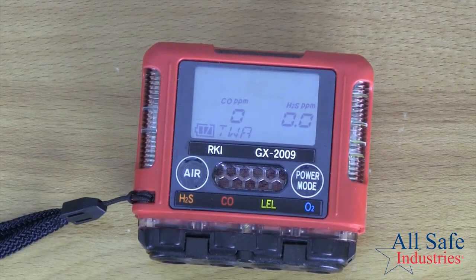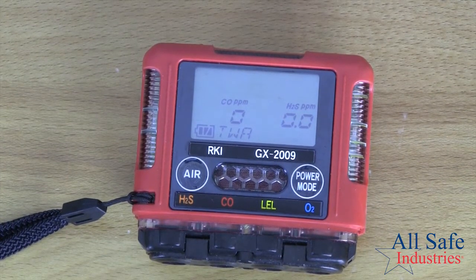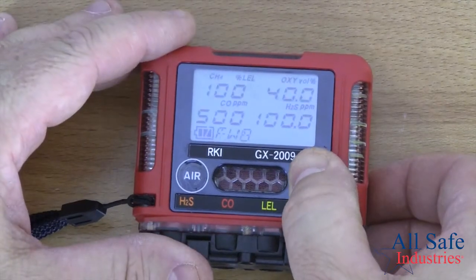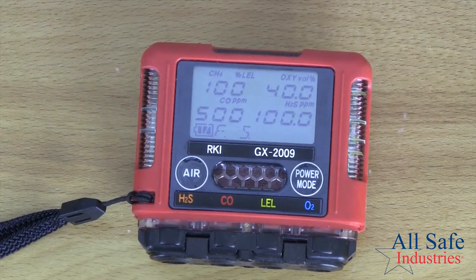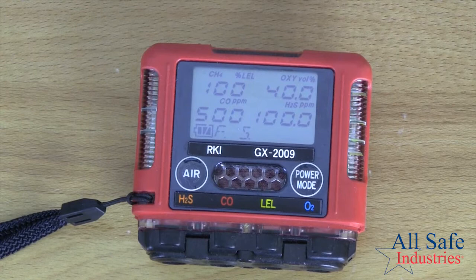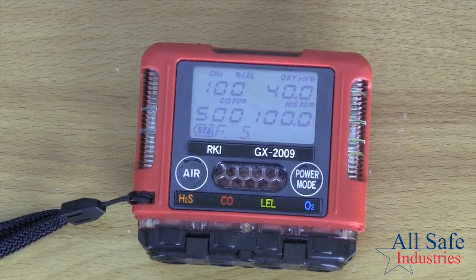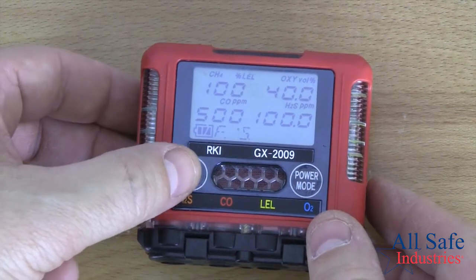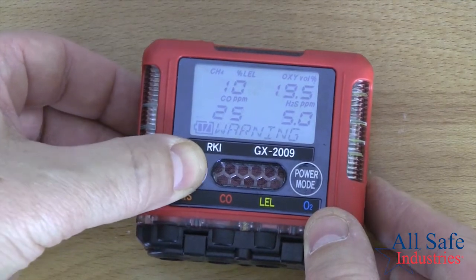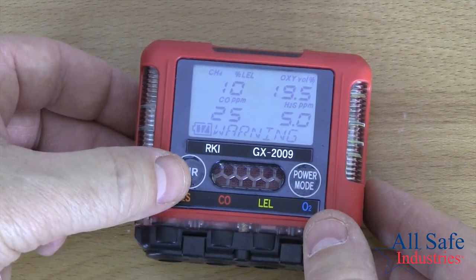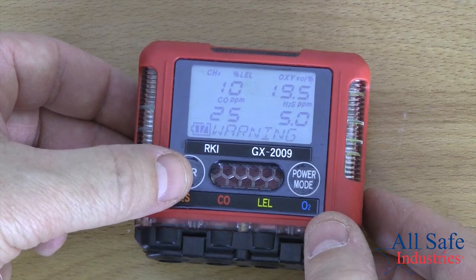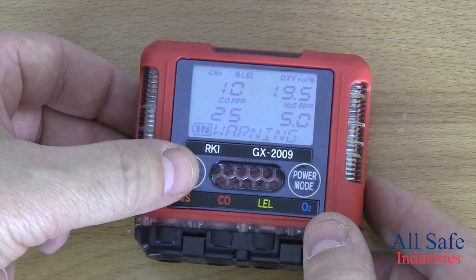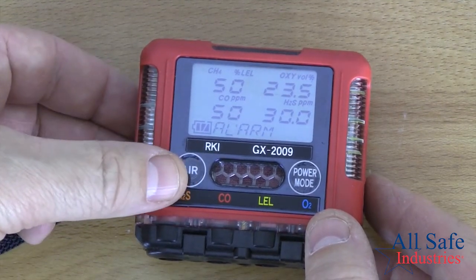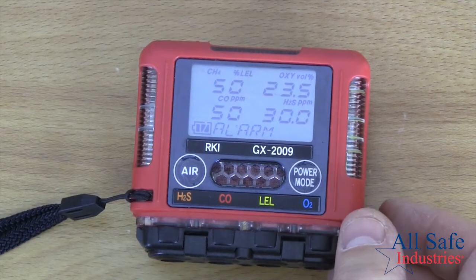The next one is time-weighted average. This is like your 8-hour alarm, and both the STEL and the time-weighted alarms only register for the toxic sensors. One more press of the button and you're going to see the full-scale reading on all the sensors. So this is as high as the sensors will go, and on this page we can actually scroll through the different alarms using the air button. So this is the low alarm or the warning alarm, and you'll see what those values are set to for all 4 channels. This is the alarm, if you will, the second stage alarm.